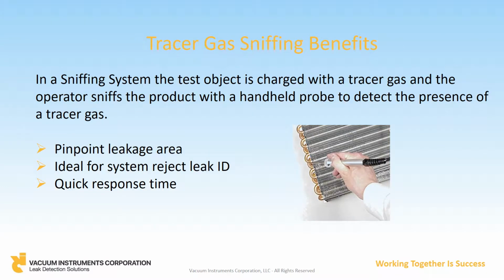Sniff testing. Here, the leak detector is fitted with a probe that allows the mass spectrometer to sample at atmospheric pressure. In practice, as was the case in the two previous examples, the object under test is first evacuated and backfilled with helium to a preset pressure. The probe is then scanned over the object. The distance from the object should be kept constant, as well as the scan speed. In application, it is good practice to limit the scan speed to 1 to 2 inches per second, while maintaining a probe distance to workpiece of 1/10 to 1/4 of an inch.